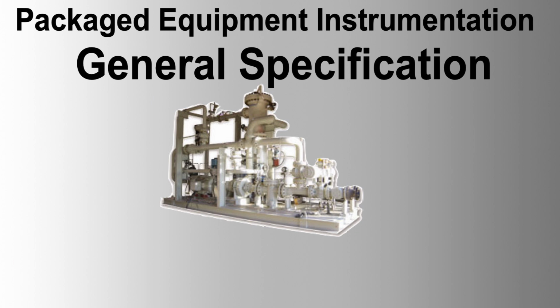General technical requirements for instrumentation for packaged equipment. General: packaged instrument and control systems shall be designed to operate within the performance limits specified or agreed by the company, ensuring minimal maintenance costs by considering the availability of skilled personnel on site. Instrument systems should be designed to avoid interaction between associated electrical circuits and suppress spurious signals that cause interference.